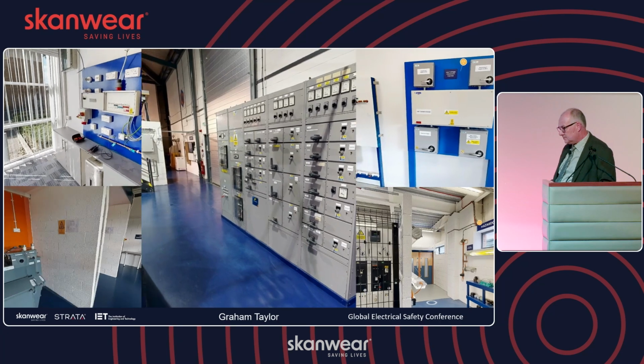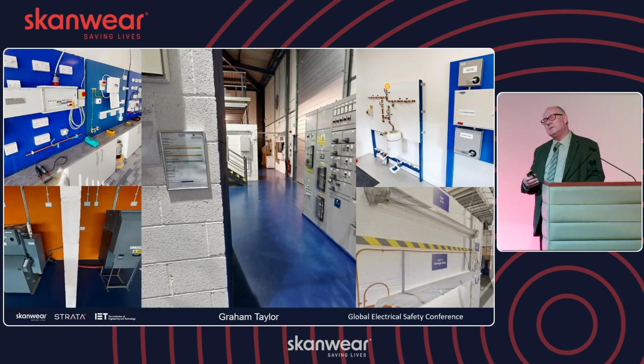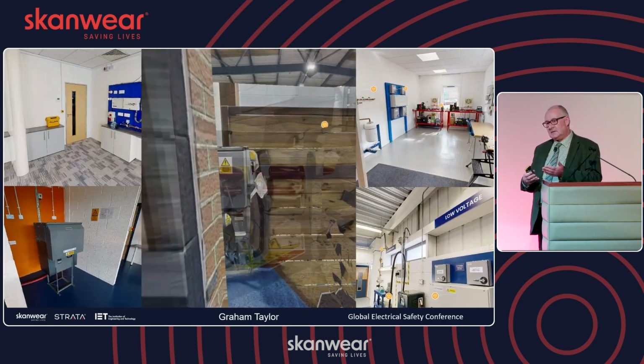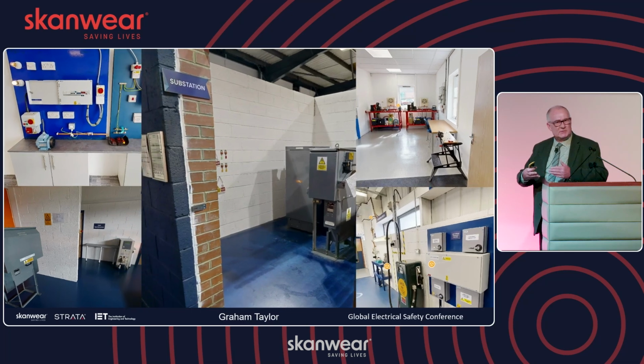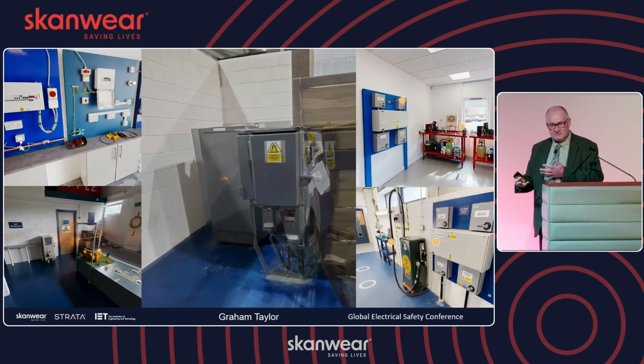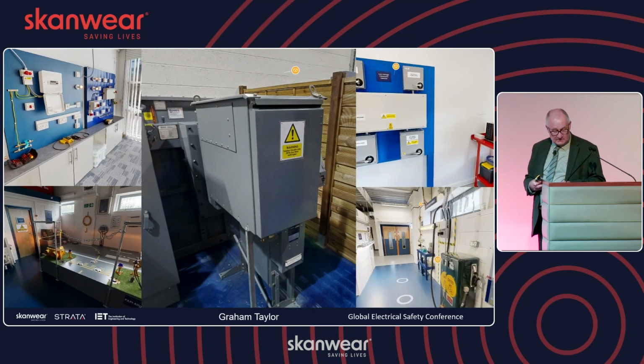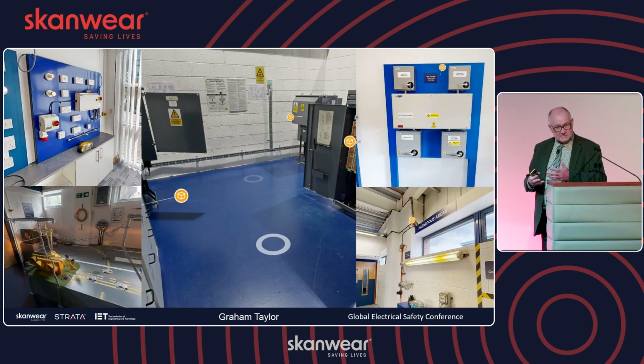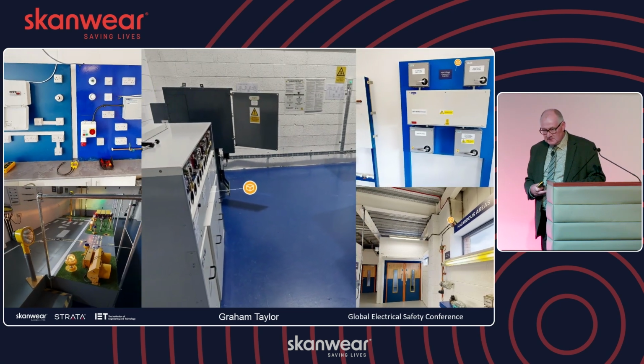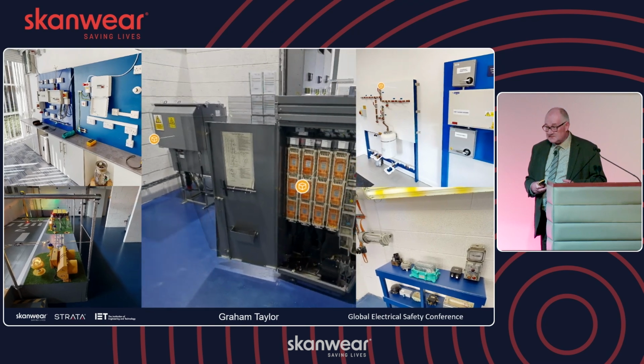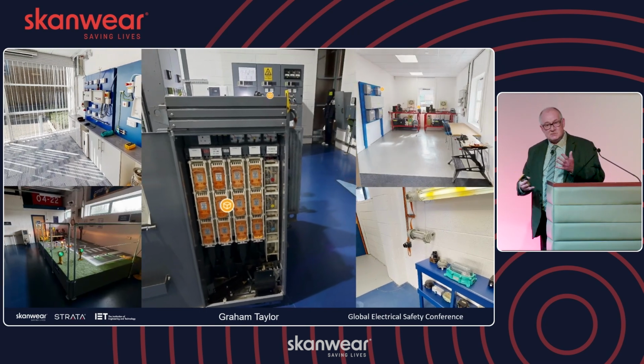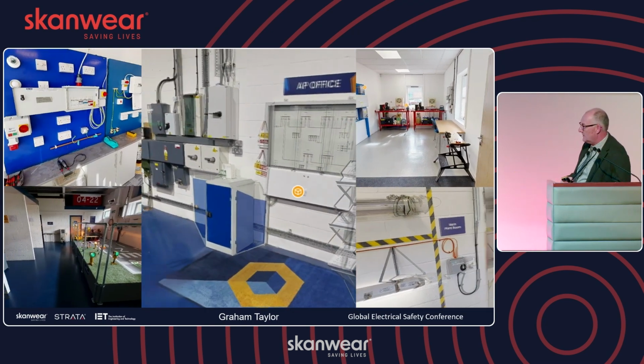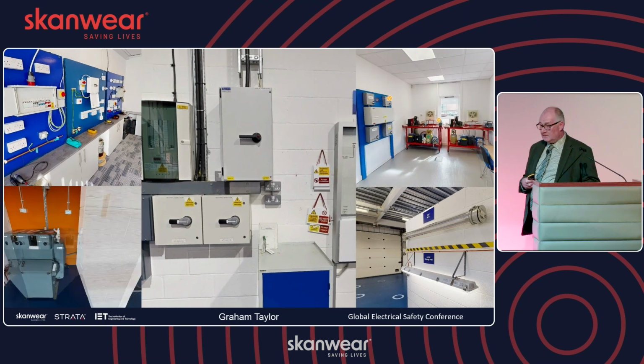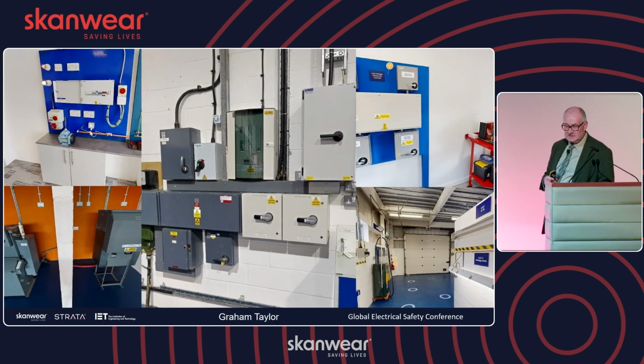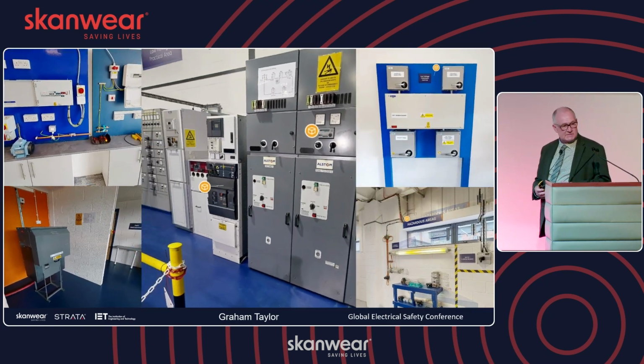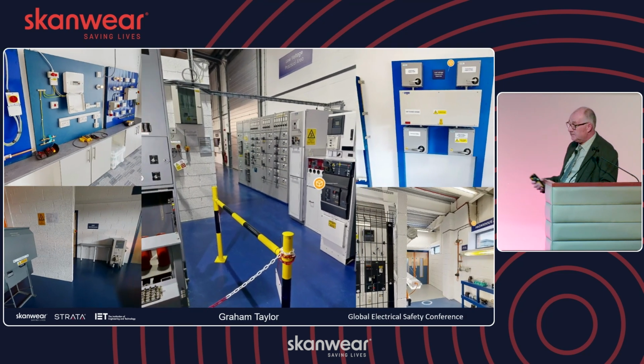When we talk about HV rings, it's by what the UK law says HV is. So we don't even talk about MV. We recognise that there's MV out there and people use that term quite a lot. But as far as the law is concerned, which is where we teach from, anything above 1,000 volts AC is HV. So usually around 11,000 volts, because that is the most common one for your private networks, and certainly what you'll find on MOD sites, hospitals, data centres, factories, maybe 33.